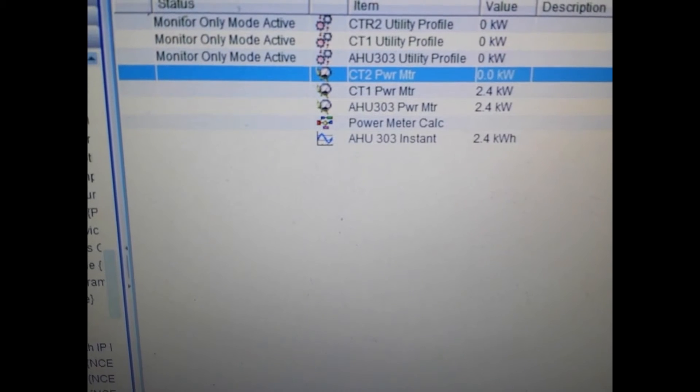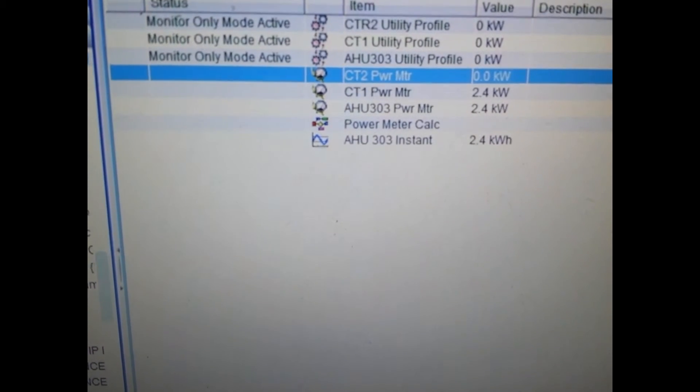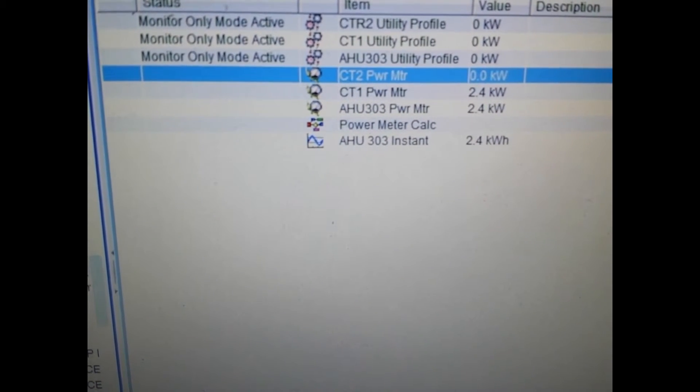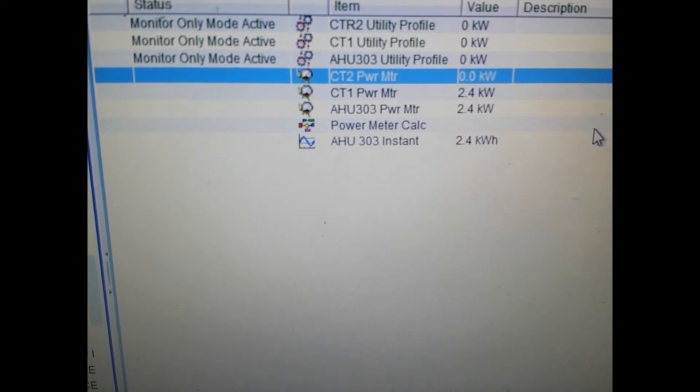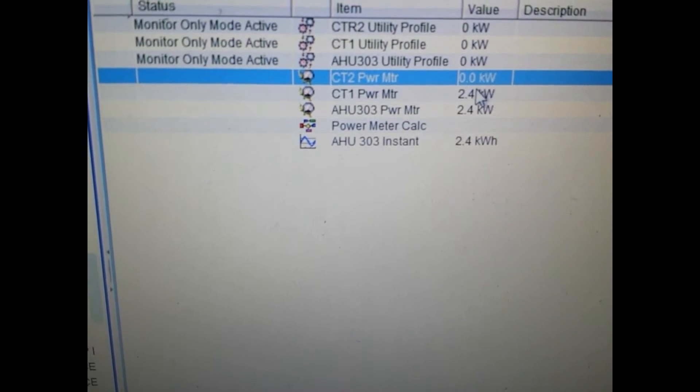On Metasys you can see that we are currently showing 2.4. You need to remember that the meter itself is live in your circuit and may show much more rapid changes in the load than what the data logger does. Depending on your meter, some meters will actually average out the load, and others like this one in this video actually show live current changes. You can see the change in the wattage demand right there on the meter.